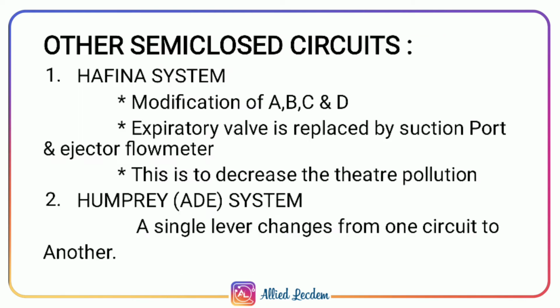Other semi-closed circuit. Number 1, Hafnia system. These are modifications of A, B, C, and D. The expiratory valve of this system is replaced by a suction port and an ejector flow meter to decrease theater pollution.